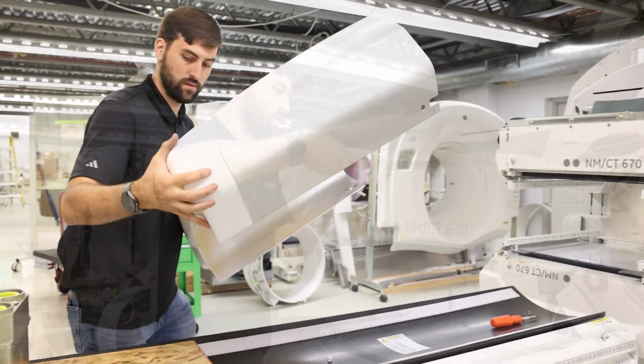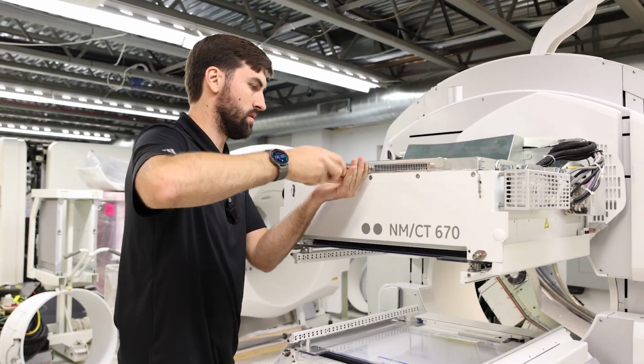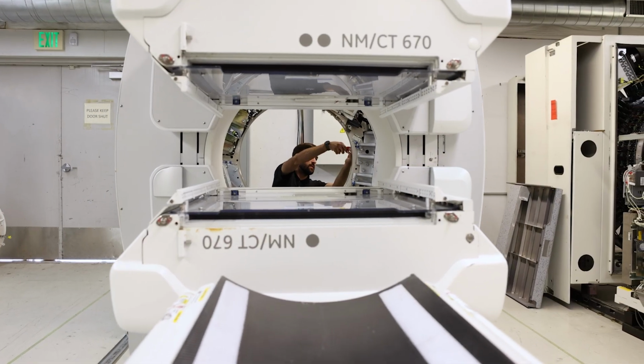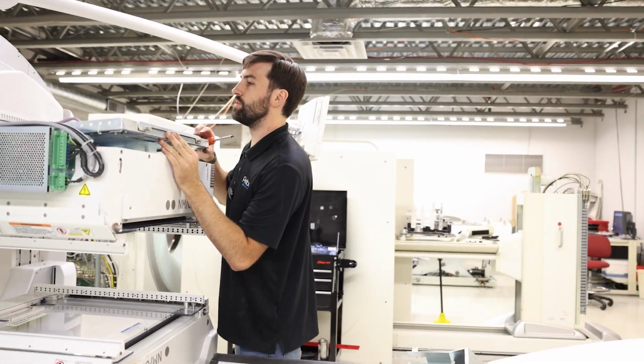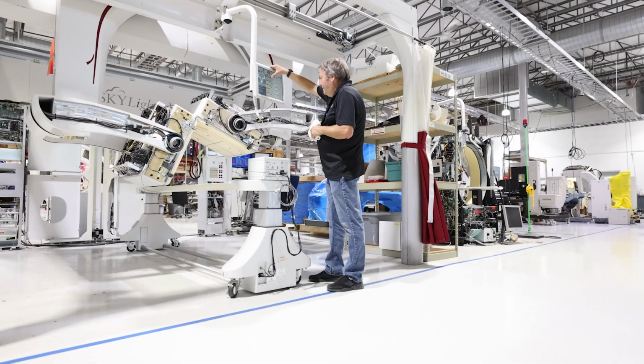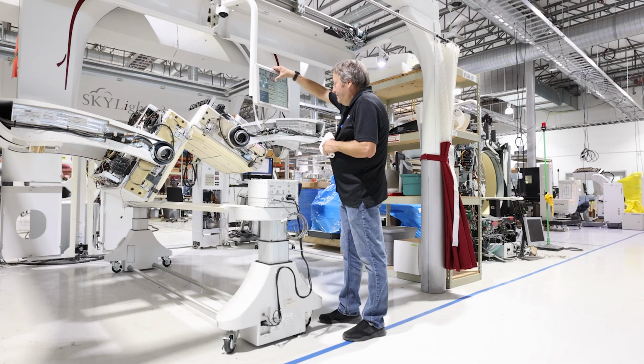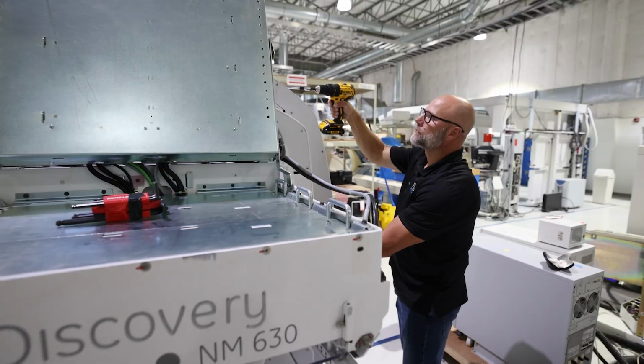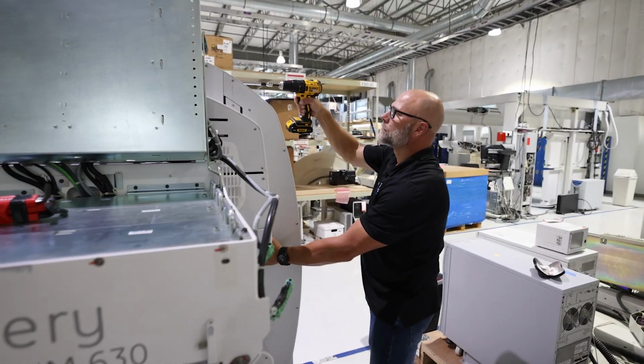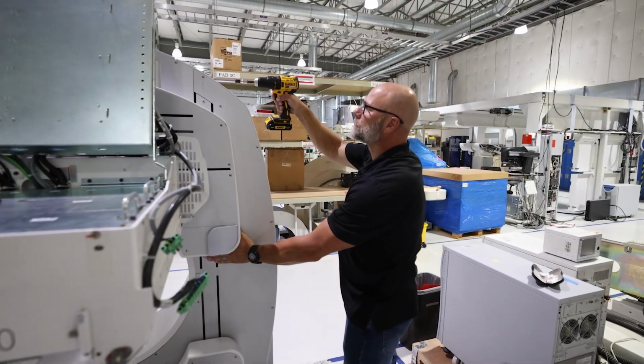We install them on the machines for testing, verify that everything's working as they should. I would say we're probably at 30 to 40 different machines, a bunch of different models from different OEMs, just to cover all of our bases and make sure we can support every machine we have in the field. We also do repair and testing as well as refurbishment. So we're repairing anything from power supplies to the detector boards, anything relating to the machine we will do repairs on as well as testing.